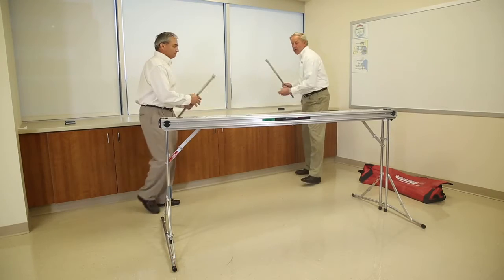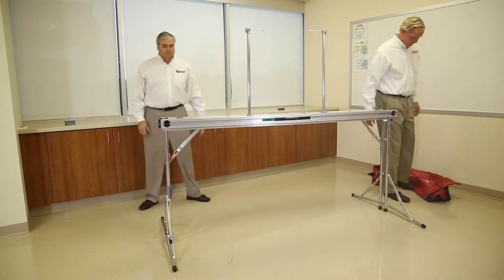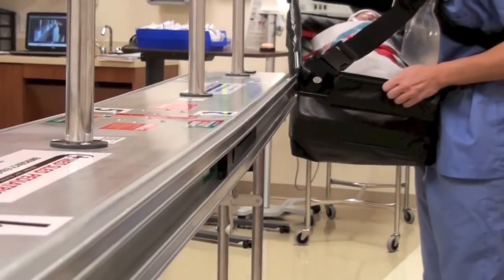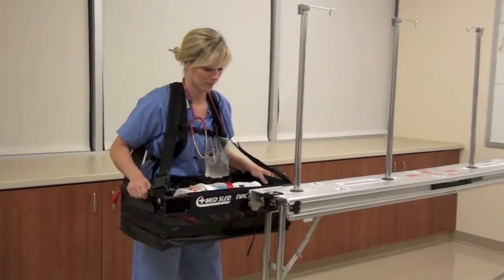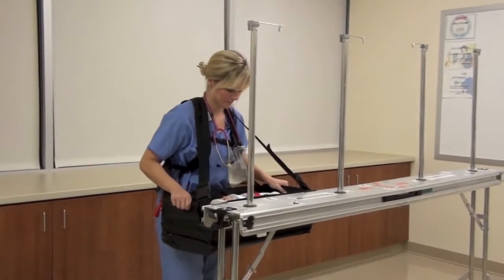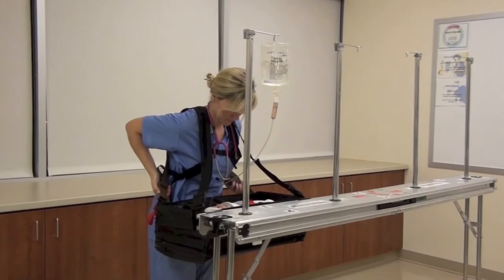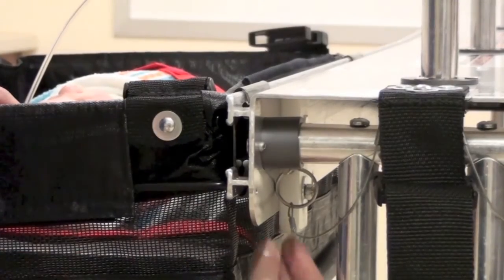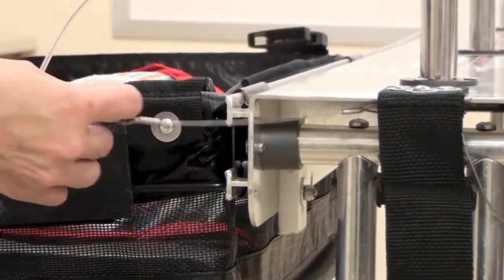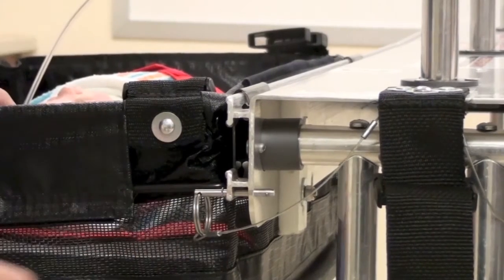The rack system allows the placement of four IV poles; two are included with each rack system. The EVAC rack holds a maximum of six baskets, three per side. The evacuator can approach the rack at either end. To secure the basket on the rack, slide the basket mounting brackets onto the rail, ensuring both brackets slide over the top and bottom rails. Once the baskets are securely on the rack, hook the IV bag to the appropriate pole, then unbuckle the vest from the basket. After loading a basket, secure it in place by inserting the locking pins. There is a locking pin located at the end of each rail; all four pins should be in place whenever baskets are on the rack.